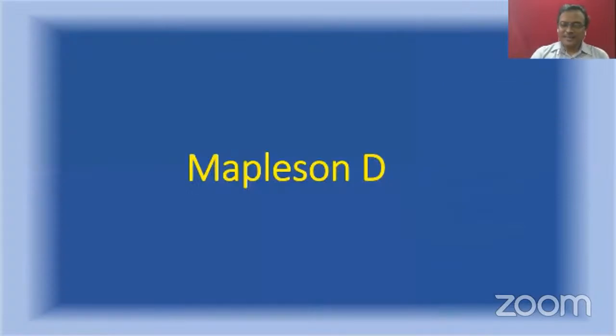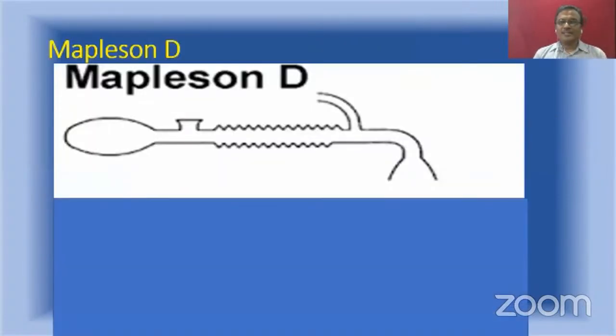Let's move on to Mapleson D. So there is a striking difference between the earlier systems and this one. Here you can see the fresh gas is close to the patient and the valve is away from the patient. That's a major striking difference between the earlier circuits and this one. The fresh gas flow has come close to the patient while the valve has been moved away from the patient.